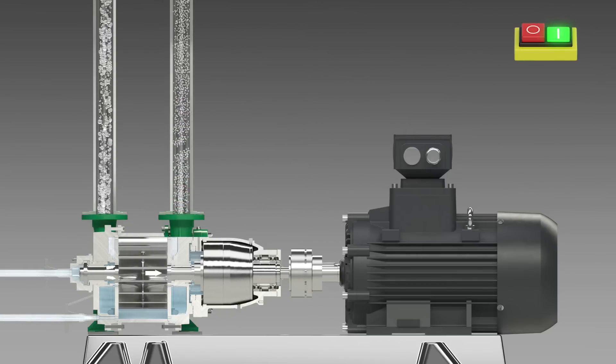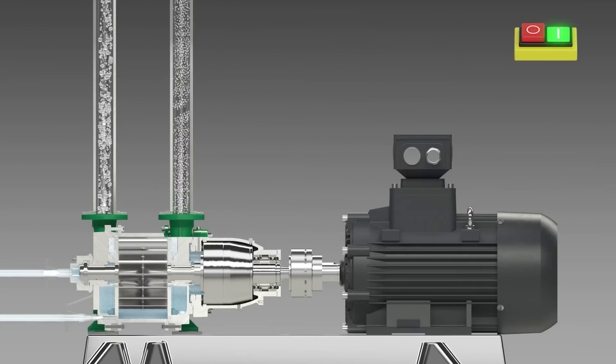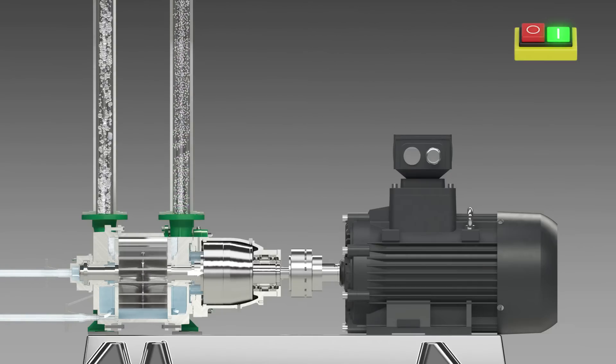A partial flow of the operating liquid is taken from the region of the magnetic coupling for lubricating the plain bearings and dissipating the heat and is then returned to the pumping chamber.